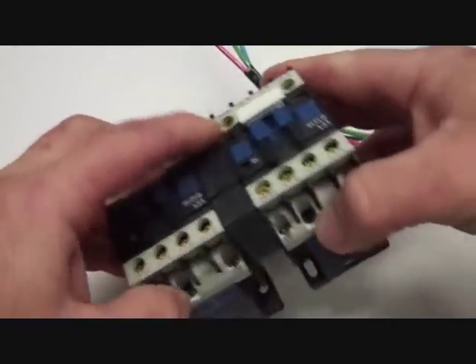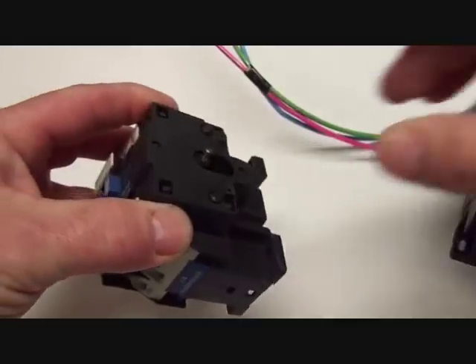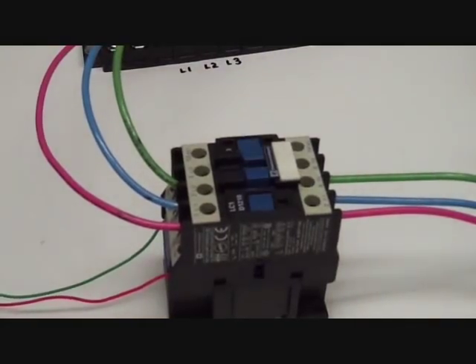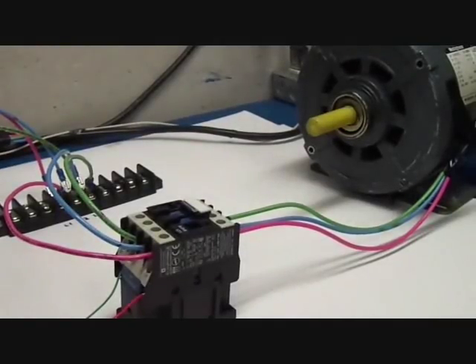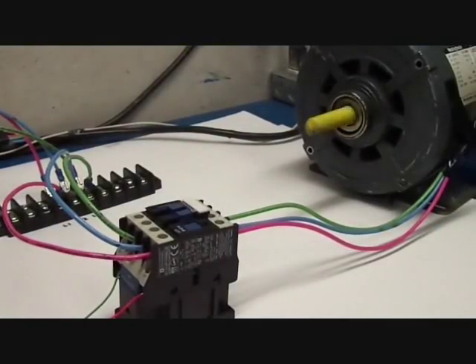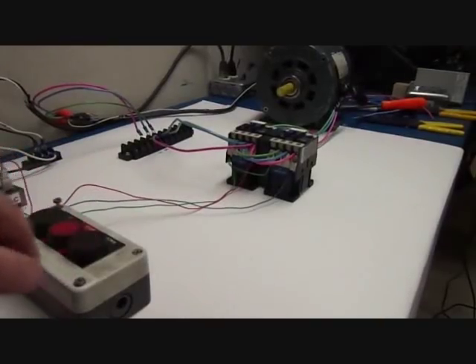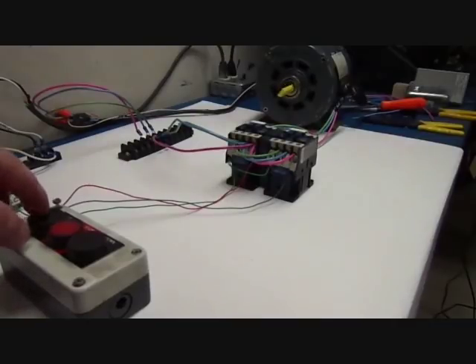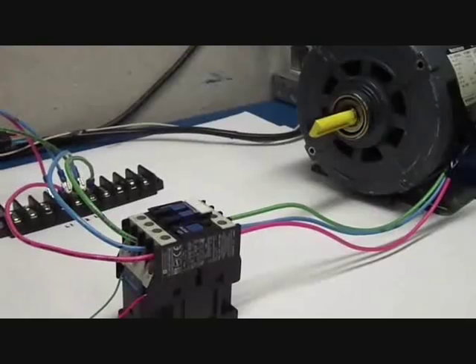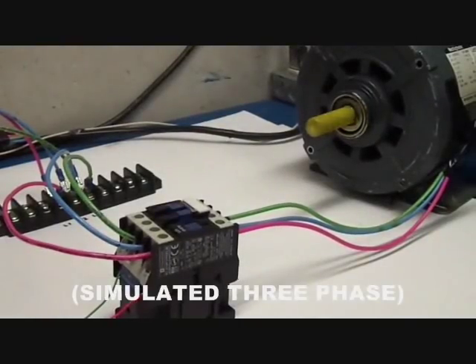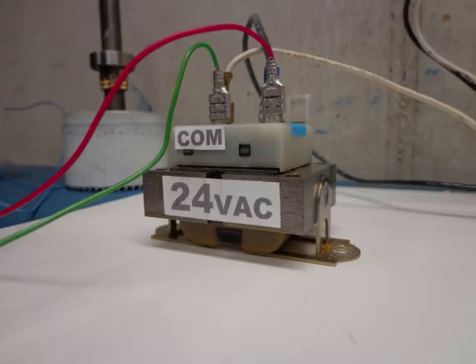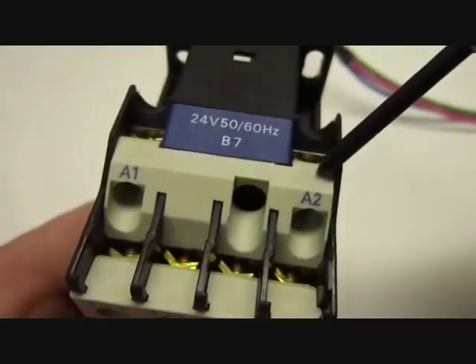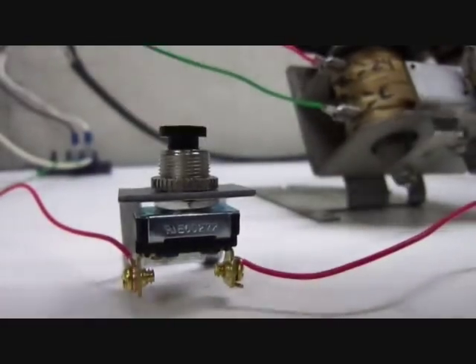Here's a more modern contactor with two coils and two sets of contacts. This one side with one coil is a contactor. This is what you would have for a motor that only needs to run in one direction, like a compressor. Two contactors joined together with an interlocking device make this a reversing contactor for motors that need to run in both directions. Right now, we're just going to use one side of it to run this three-phase induction motor in one direction. I'm going to connect 24 volts to the coil terminals labeled A1 and A2 with a push button to start and stop it.